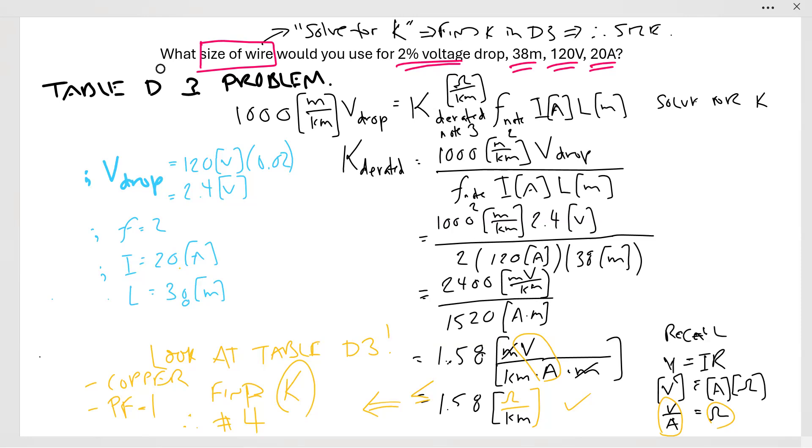Finding the size of wire when you know the voltage drop is not that difficult. We're just using table D3, which really has a governing equation. Keep your units, let them do your checking for you, and you should be good to go.